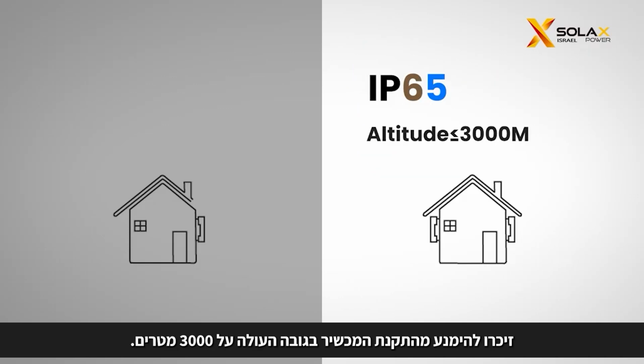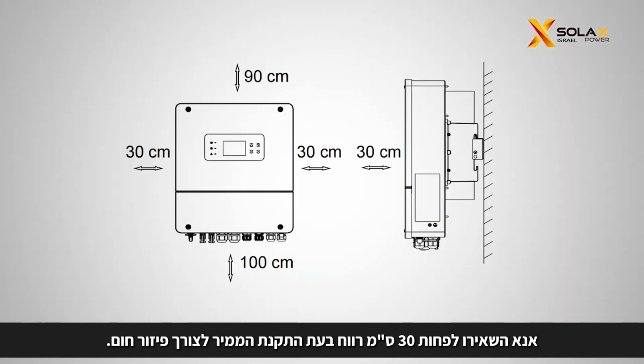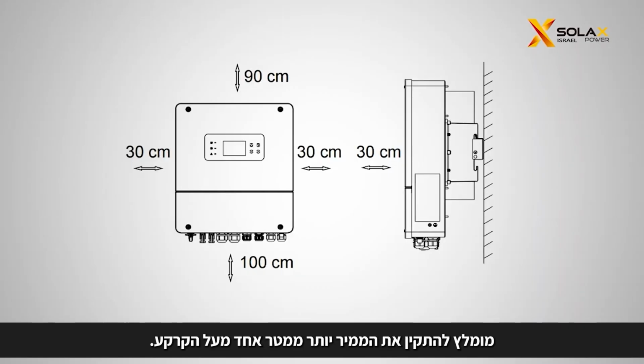Remember to avoid installing the device at altitudes exceeding 3,000 meters. Please reserve at least 30 centimeters of space when installing the inverter for heat dissipation. It is recommended to install the inverter more than 100 centimeters above the ground.